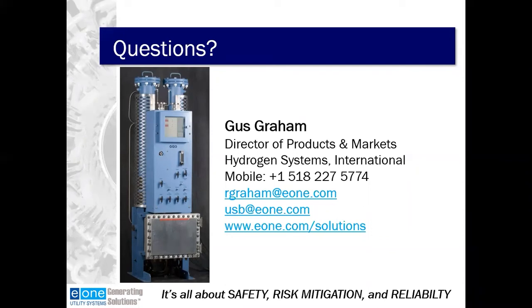So the question about the inlet dew point on a gas dryer: if you have a large leak in your generator, a clip leak on a stator water cooling system or a hydrogen cooler leak tend to be the larger leaks of water into the system. The dryer may not be able to regenerate quickly enough to keep up with the water ingress, so at that point the dew point rises. So I would think the trend is more the thing you want to be looking for. If your inlet and outlet dew points are trending up instead of trending down or stable, that would be the indication that you have an issue with your generator, because the absolute dew point that it operates at will be conditional upon how much water is getting into the generator.